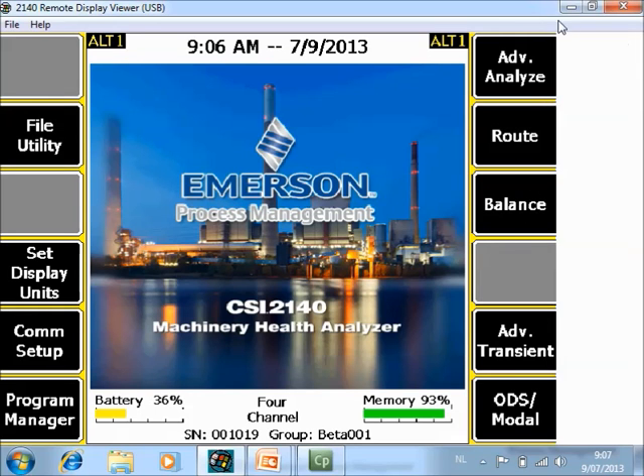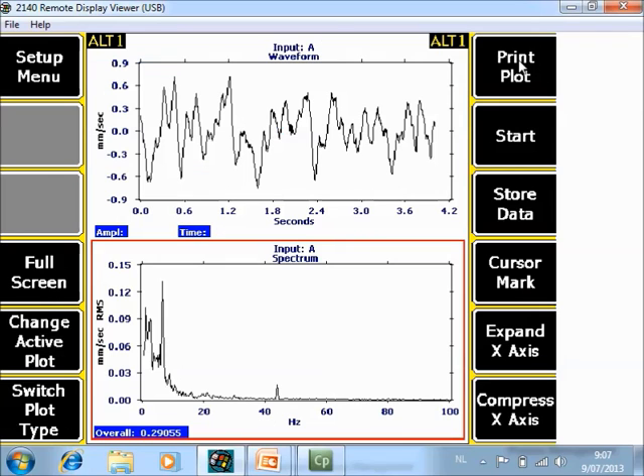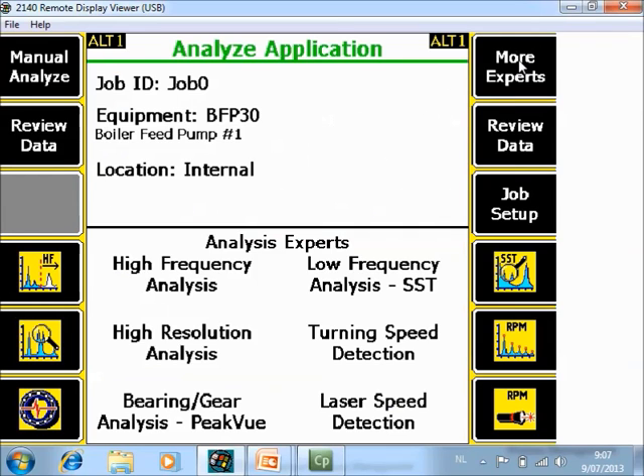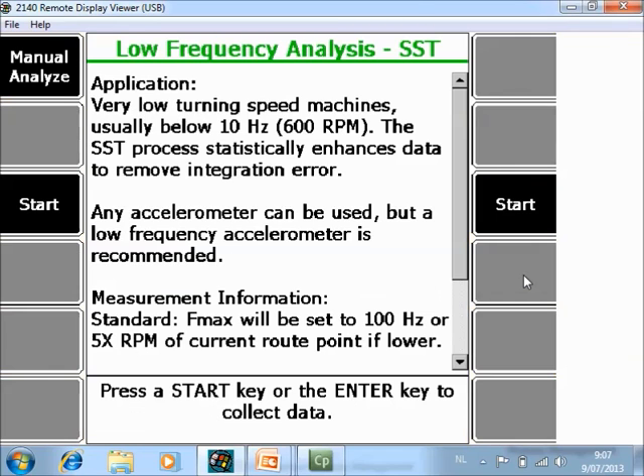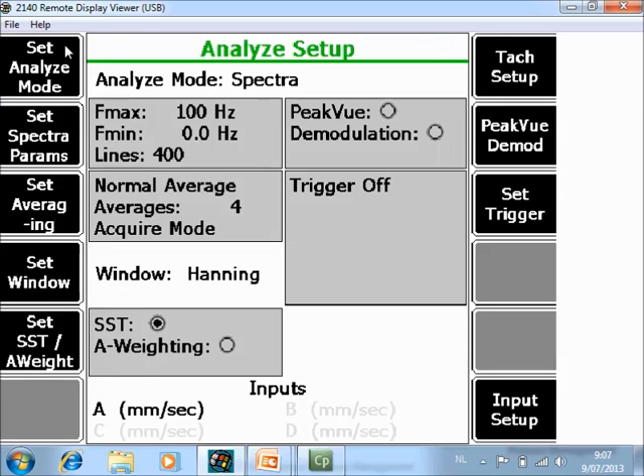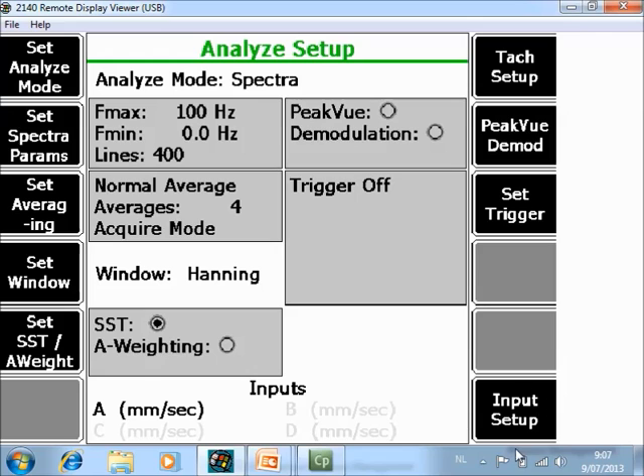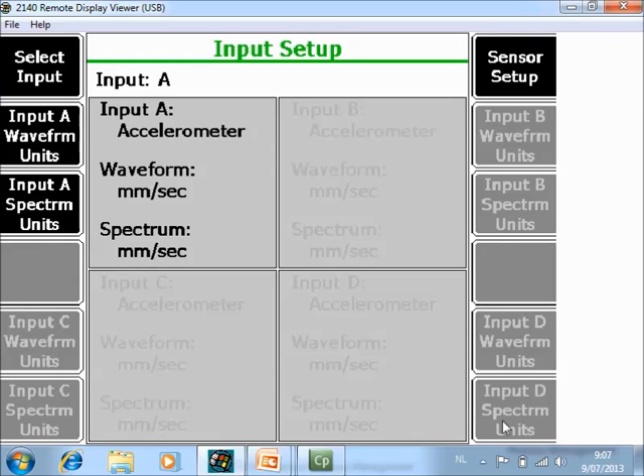On the home screen I go to Advanced Analyze, then to Low Frequency SST. Instead of starting immediately, I first go to Manual Analyze. The default value here will be to work with one input. To measure several sensors simultaneously, go to F12 Input Setup.